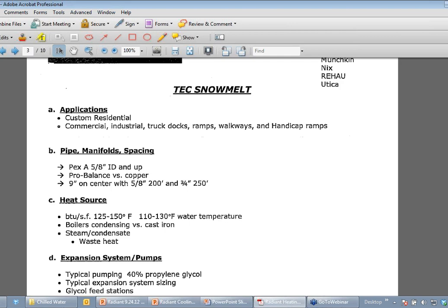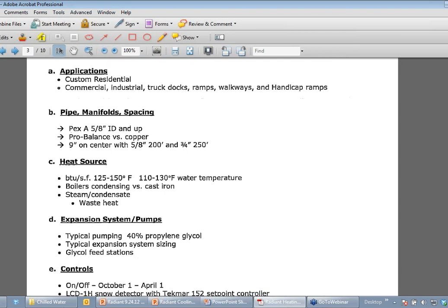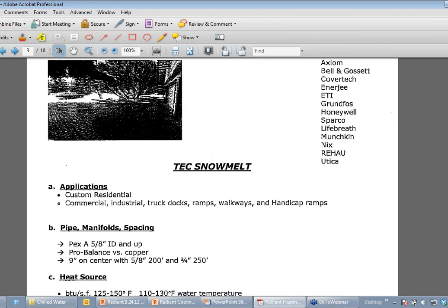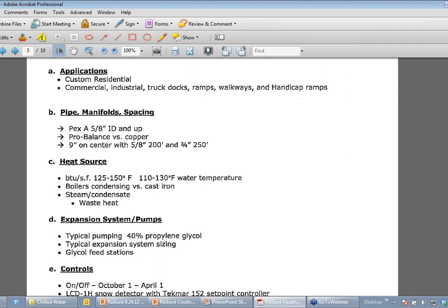The lower the water temperature, the higher the flow rate you'll need. But for a generic system, this is the snowmelt cheat sheet Bill has. For a generic system, let's just say 120 degree water temperature might be your design.